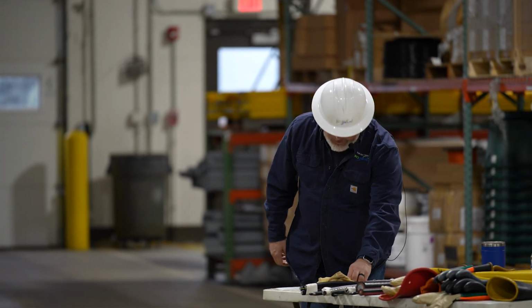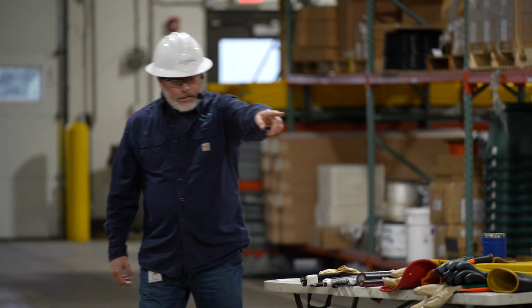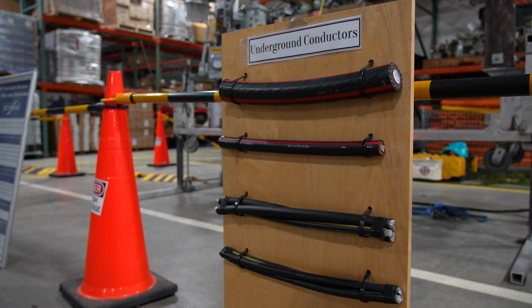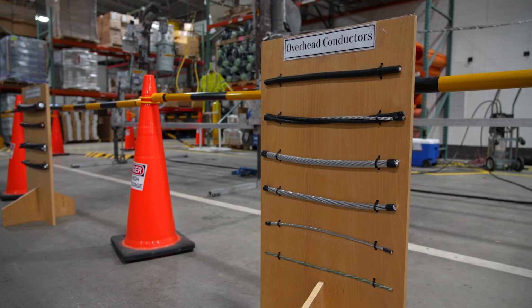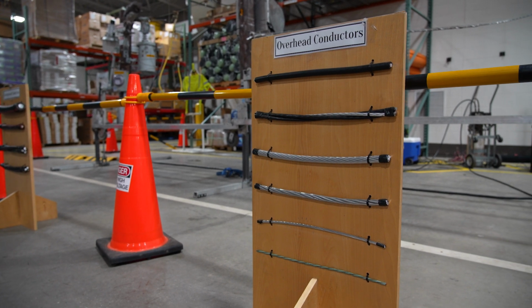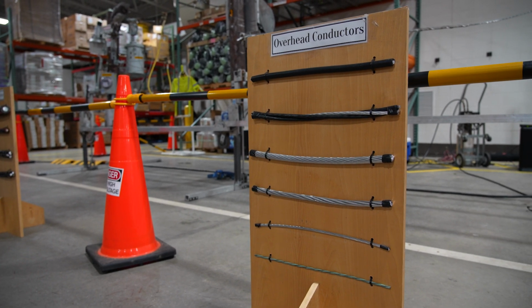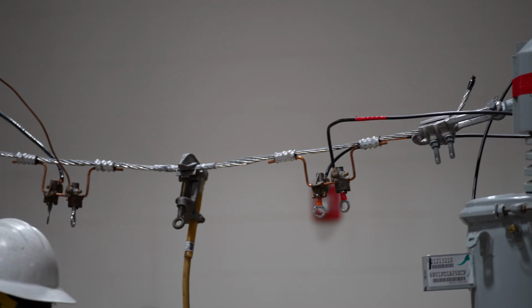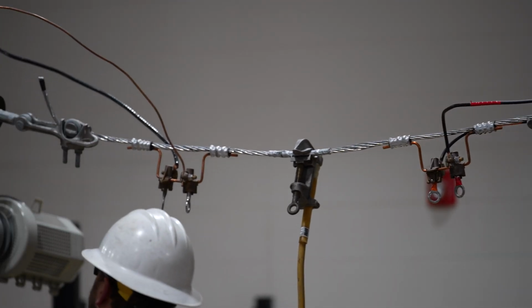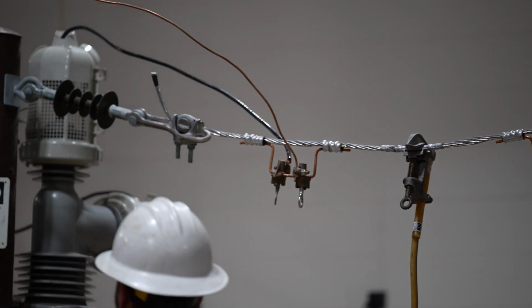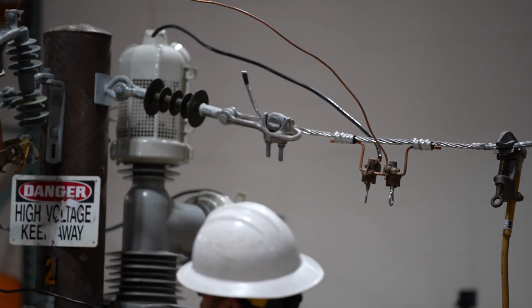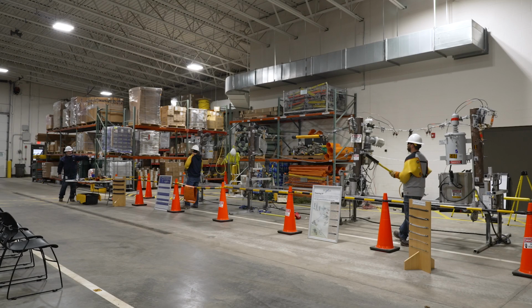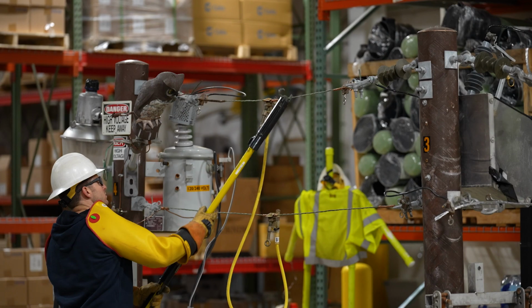A little bit about some of the table items here. As you can see up here, we've got our different wire sizes, and there's a myth with our wire that's in the air, that it's insulated. It's not insulated. There's another myth that there's 240 volts going across the top. That is also false. There's 7,200 volts single phase, 12,470 volts phase to phase. And phases is what's carrying the electricity. We've got a phase and a neutral up here.